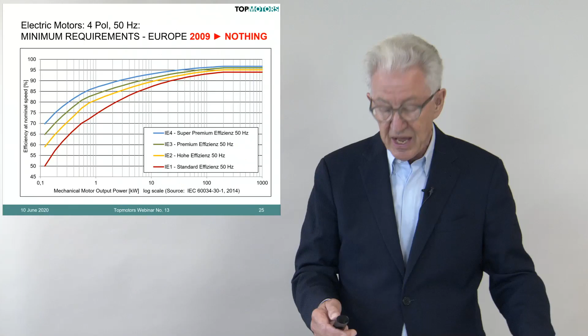These curves are shown with the horizontal axis in a logarithmic scale. On the left you have 0.1 kilowatt, and then steps of 1, 10, 100 and 1000 kilowatt to the right side. And you see what everybody knows, that the efficiency of a small machine is much lower than the efficiency of a bigger machine. You also see that these four curves, which have a wide spread at the small sizes, converge to within a few percentage points on the right side above 200 kilowatt. And now, status of 2009: the IEC standard was issued, but requirements, nothing. Now we go forward.